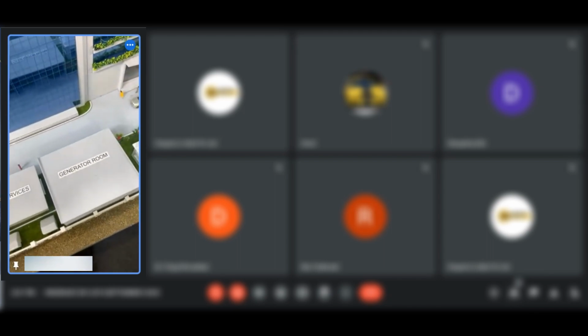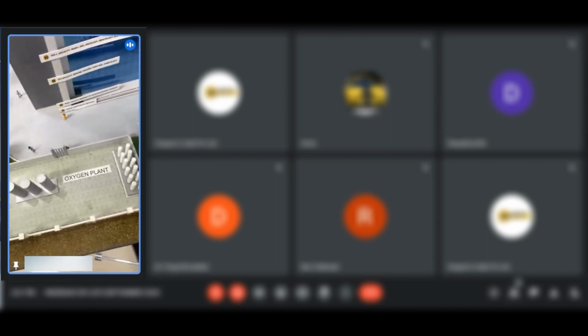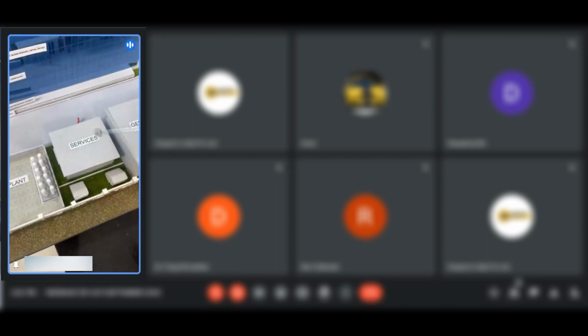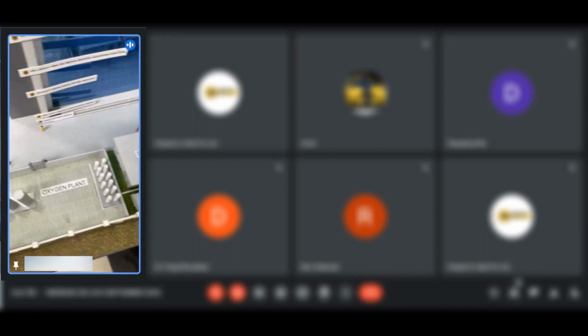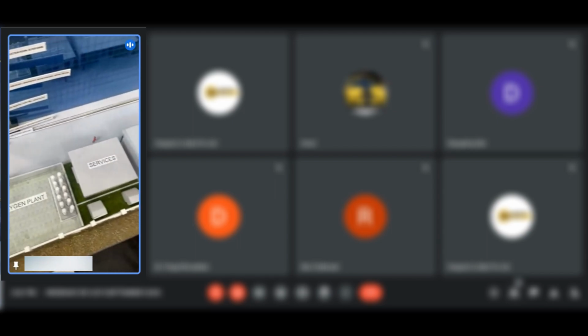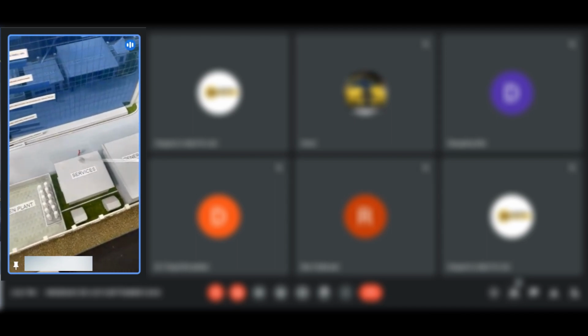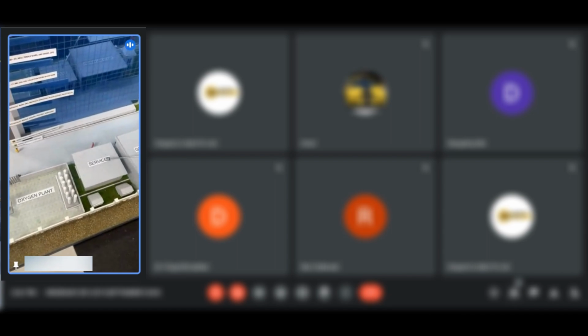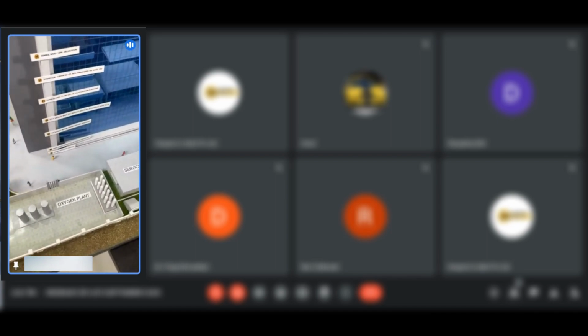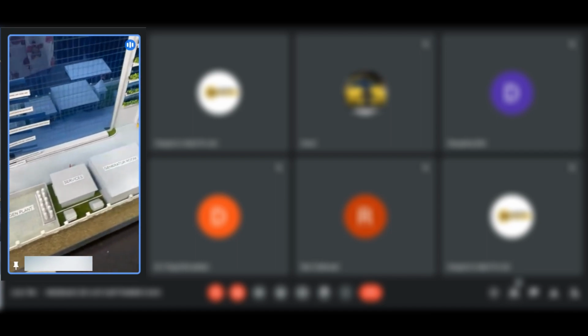So the next would be our generator. So we've provided a generator room. If you see here, we've provided an oxygen plant in the far corner, and then we've provided a services block. What we've done is provide a buffer area in between the generator room and the oxygen plant. We've provided a service area. We've given a staff locker, change and staff areas and everything. So this can be central, so the staff can keep watch on both the areas. Yes. So now the generator room.